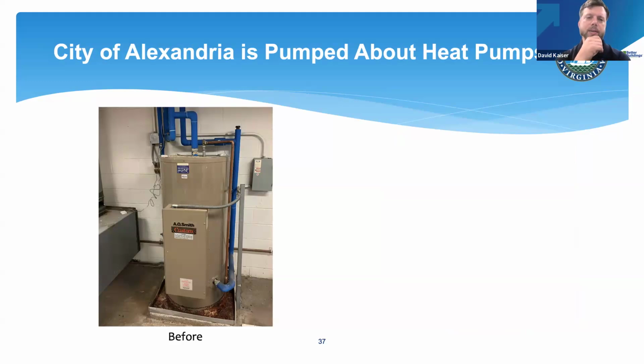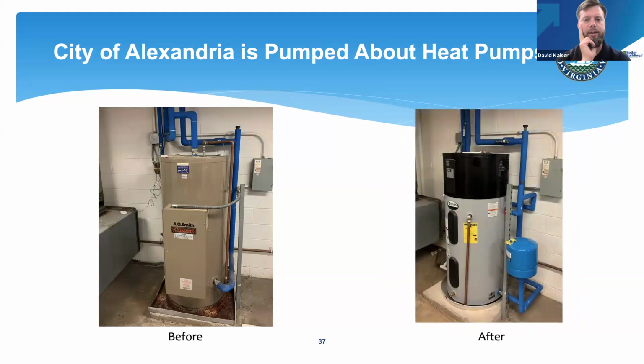Next view. And again, a large hot water tank, and then changed out to a reduced size hot water tank. This was in a library and had a recirculating loop that was on all the time. The use case was just for lavatories in the bathrooms, and one small kitchen sink for the staff. And so when we did this, we didn't really need that recirculating loop going all the time. There's just not much risk associated with having a pump be off on occasion when the facility is not used. So that's actually a key concept when you don't have showers in place that might be related to more health standards.